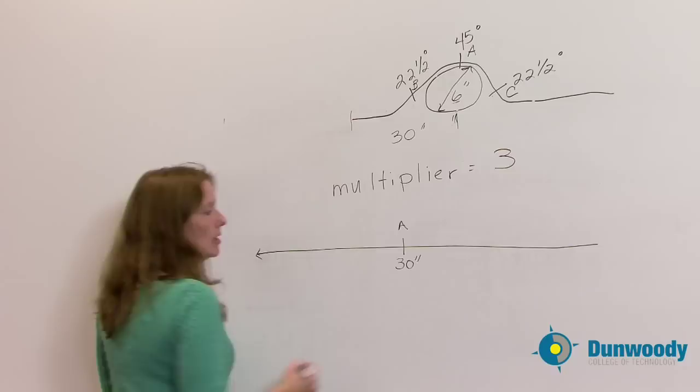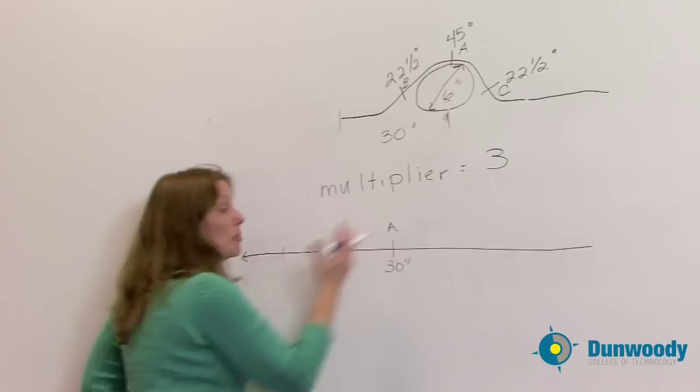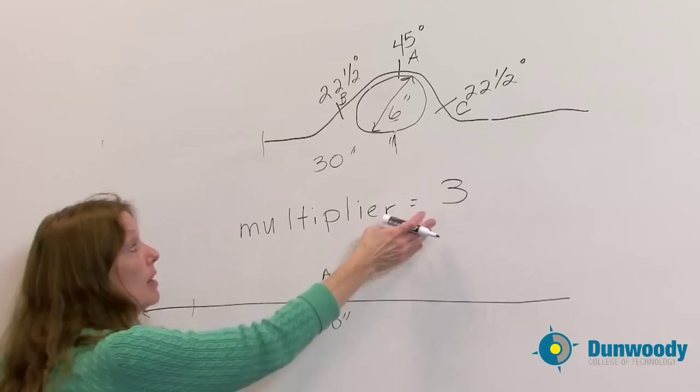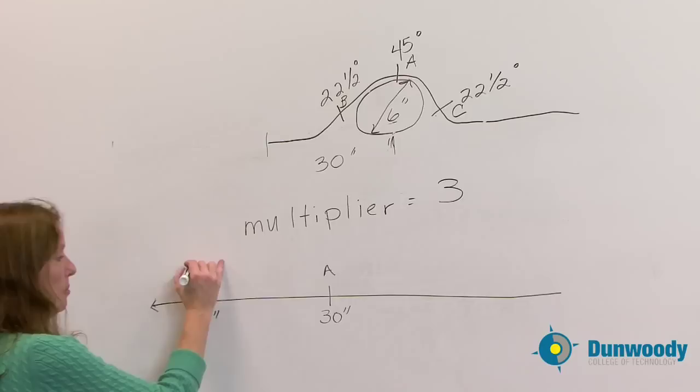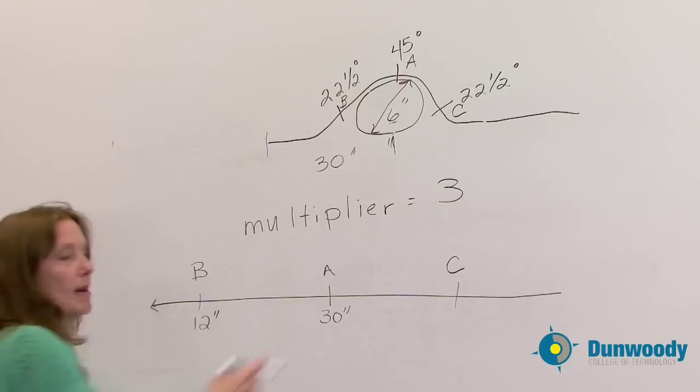And then I'm going to mark my mark B because it's a six inch obstruction and because I'm going to bend it all in the same direction, I'm going to take three times six, 18 inches. So I'm going to subtract 18 from the 30 to give me 12 inches. That would be my mark B.